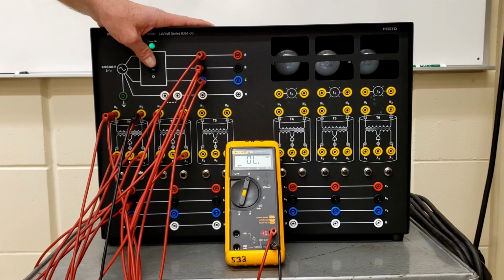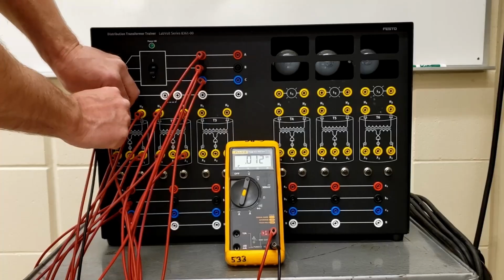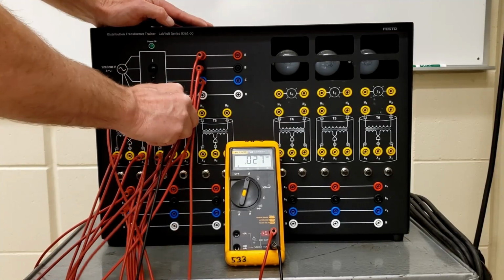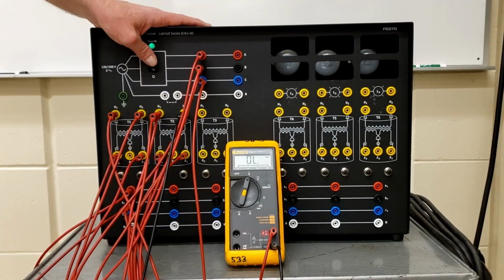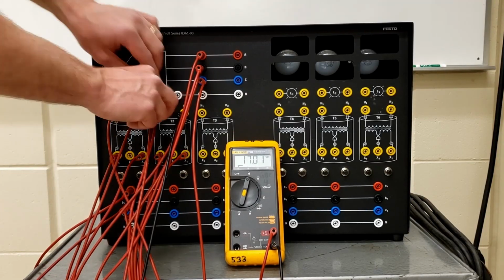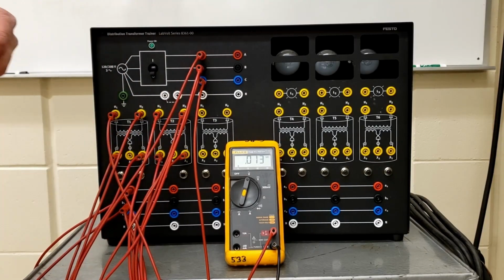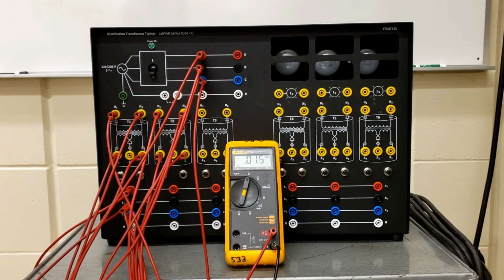Okay, so we're on AC voltage. We got 208, 210. Okay, beautiful. So that's one winding. Second winding here should have 208 applied to it as well. Beautiful. Okay, and then our secondary windings are each 120.